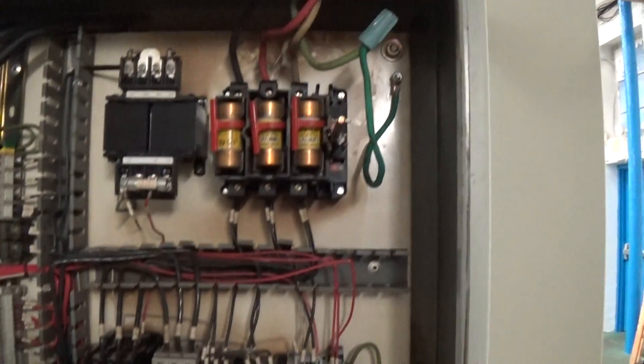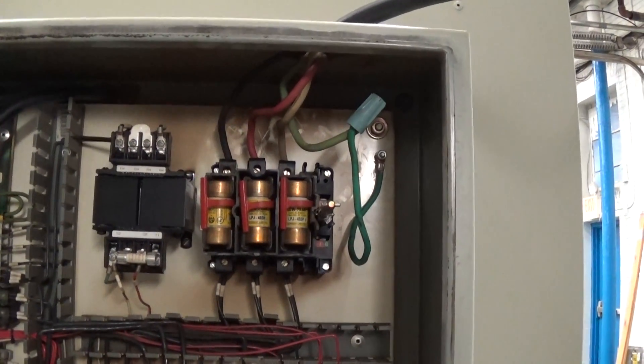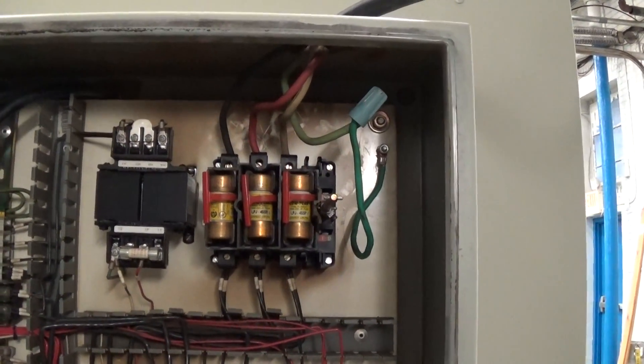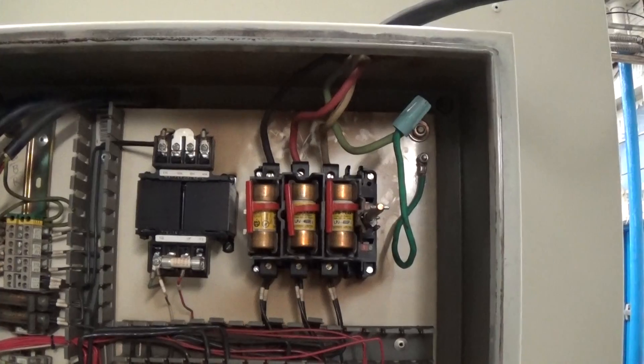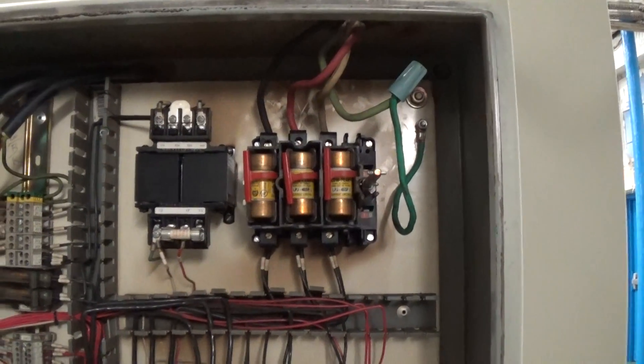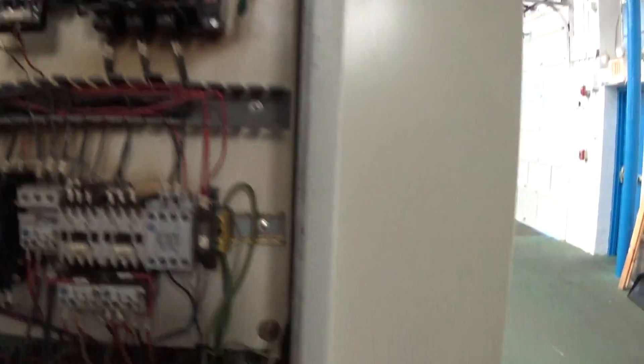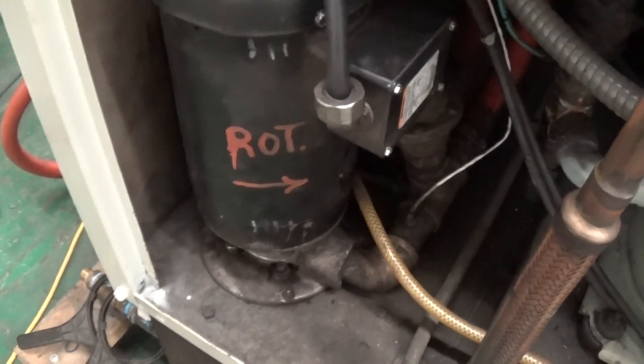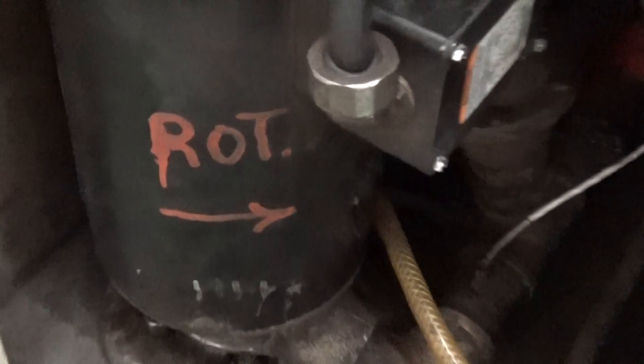But when you do power this unit up, 460 volt, 3 phase, it is rotation and phase specific. So the easiest thing is to either double check with somebody looking at the fan rotation from above or the pump is labeled here for rotation. And if somebody bumps the contactor, you can confirm that rotation.